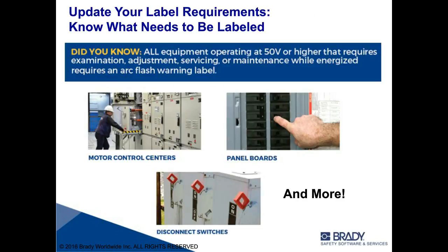Before talking about what's on the new labels, it's important to talk about what needs to be labeled. NFPA 70E and the National Electric Code both use fairly vague verbiage. When you look at the code, they say equipment such as switchboards, panel boards, industrial control panels, meter sockets, and MCCs shall have these warning labels on it that tell people what the hazards are. That vague terminology allows for some interpretation, and some people start to wonder, well, what actually needs to be labeled?